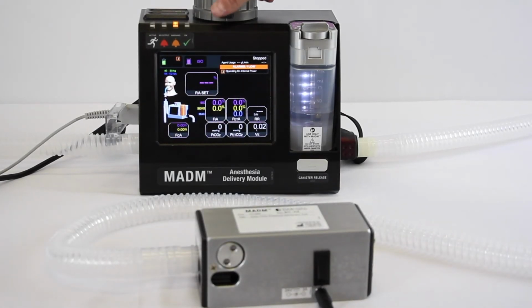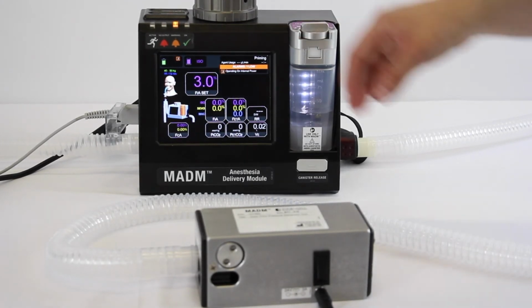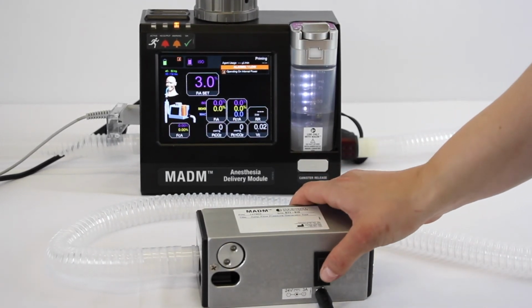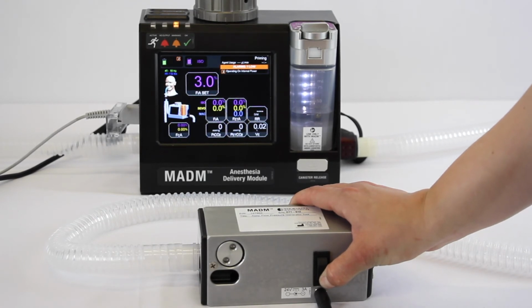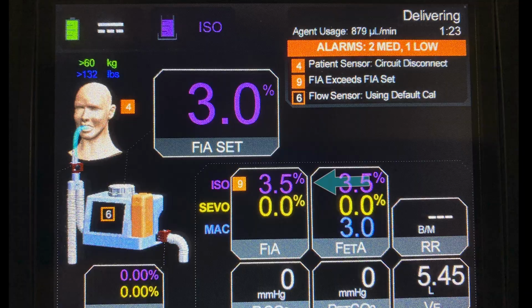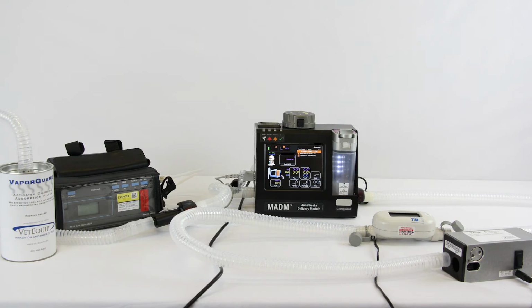After confirming flow accuracy, use the dial to set the target anesthetic level to the value indicated in the service manual. Continue providing flow with the adjustable flow source and wait for at least 1 minute. Compare what is indicated as the inspired anesthetic concentration on MADM with the reading on the external anesthetic gas analyzer. This test is completed for both isoflurane and sevoflurane, at low and high flows, and at low and high inspired set anesthetic concentrations.